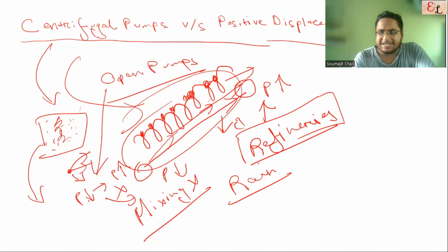And that was it. That is the difference between a centrifugal pump and a positive displacement pump. To summarize, one gives a very high discharge pressure by accumulating the fluid, the positive displacement pump, and then delivering at high pressure, creating alternative cycles of discharge. On the other hand, centrifugal pumps give continuous, high capacity at lower discharge pressure, continuously serving by giving a velocity, which is converted into pressure energy, my friends. So the two working principles are completely different, and the two use cases are also different. They can be used in series and parallel to achieve the high pressure as well as the high capacity.